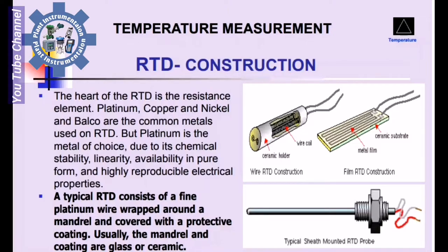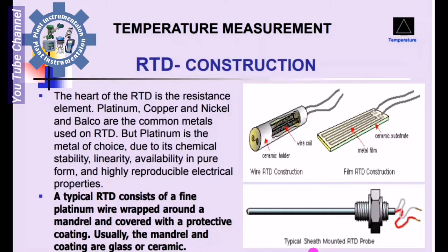A typical RTD consists of a fine Platinum wire wrapped around a mandrel and covered with a protective coating. Usually the mandrel and coating are glass or ceramic. RTD construction includes Ceramic Holder, Wire Coil, Film Coil, Metal Film, and Ceramic Substrate configurations, as seen in a typical sheath-mounted RTD probe.